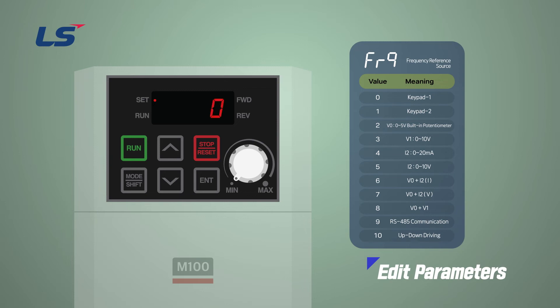When entering the edit screen, the previously set value blinks. Here, the meaning of the numbers is the same as the table shown on the screen. That is, if it is 0, it is set as Keypad 1, meaning the frequency set by the keypad on the initial screen is used as the target. We will not change this parameter.